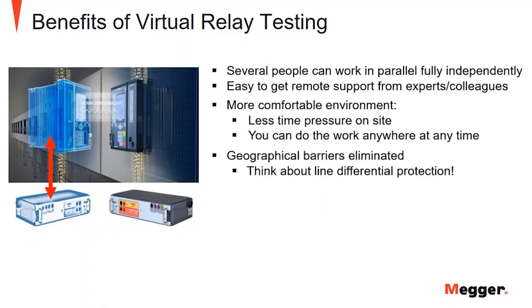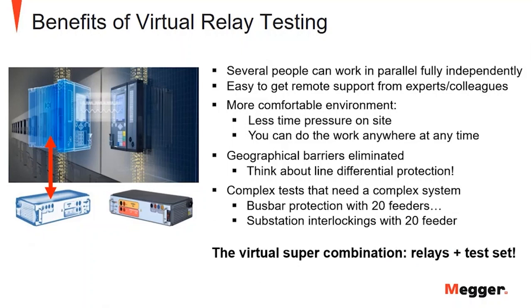Verify some things. Geographical barriers can be eliminated. Think about line differential protection, where we have two relays at both sides of the line: we can put them in the same virtual environment and perform many tests that are not based on a perfect simulation of the communication line between them. And also we can do tests that we couldn't do before because they are too complex to physically manage. We can generate a virtual relay test set with 50 current generators, connect these generators virtually to the relay, and run a substation test that we wouldn't do in reality only because of the complexity.